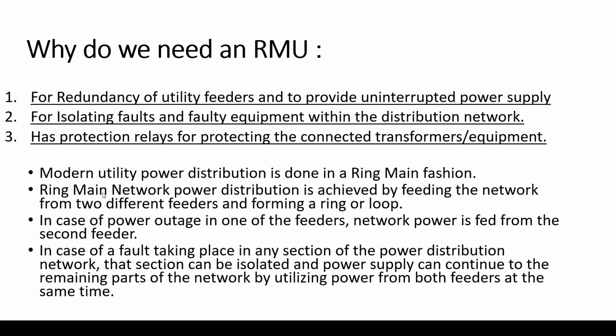So let's go briefly through these points regarding the ring distribution. Modern utility power distribution is done in a ring main fashion. Ring main power distribution is achieved by feeding the network from two different feeders and forming a ring or loop. So you provide your ring by feeding two cables from two different sections in the same substation, or from two different substations, let's say, providing more redundancy to your network. In case of a power outage in one of the feeders, network power is fed from the second feeder, as we have mentioned earlier. In case of a fault in any section of the power distribution network, that section can be isolated and power supply can continue to the remaining parts of the network by utilizing power from both feeders at the same time.